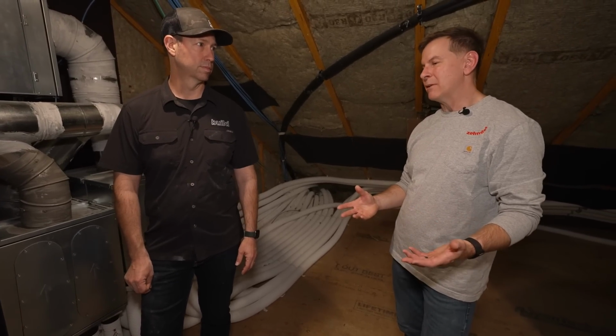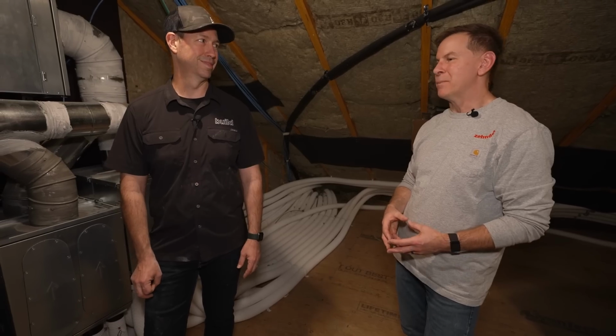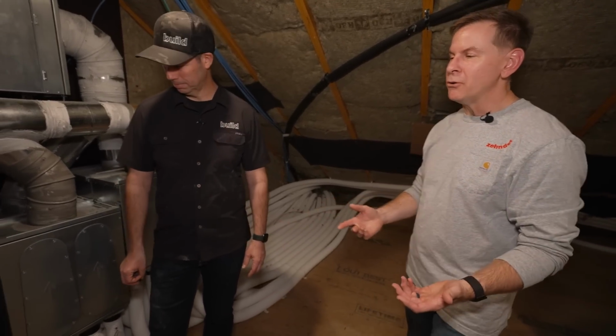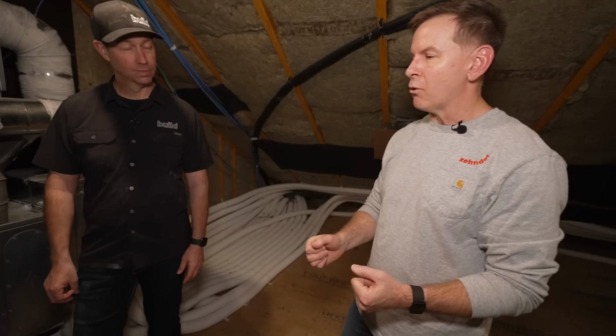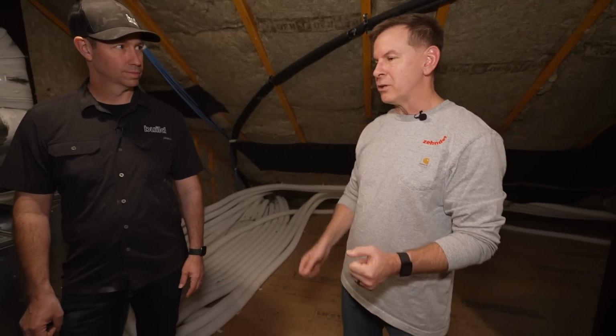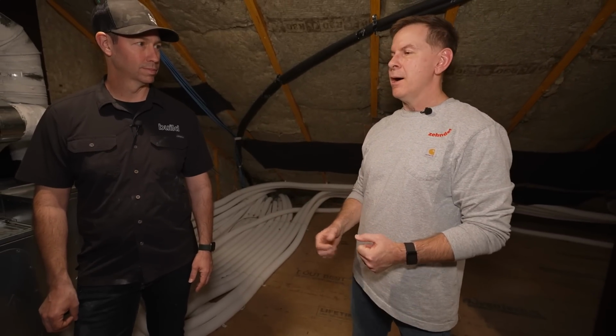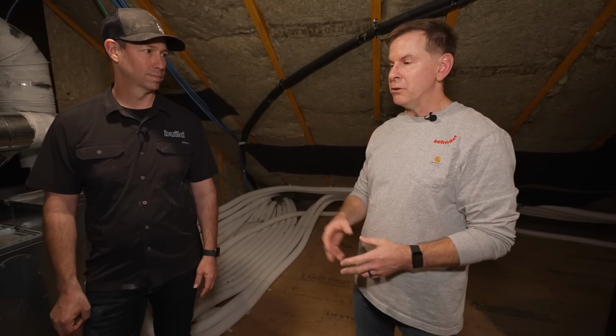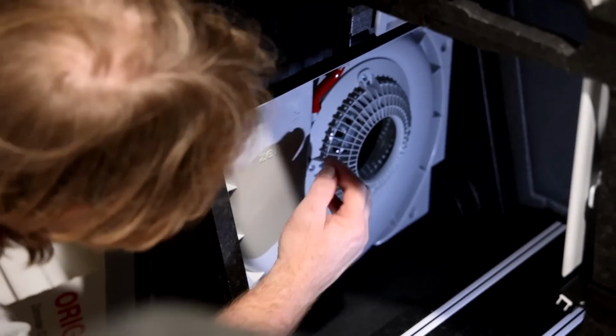We see people that let it go for 5 years and then they call up and it's pretty dirty - it's a mess. But it's not hard to do. You just open that panel up, slide the core out, vacuum off the core, give it a brush if you need to, and then you'll see the whole inside with the fan housings and where the different ducts and plenum connections are, and all those can be vacuumed out.